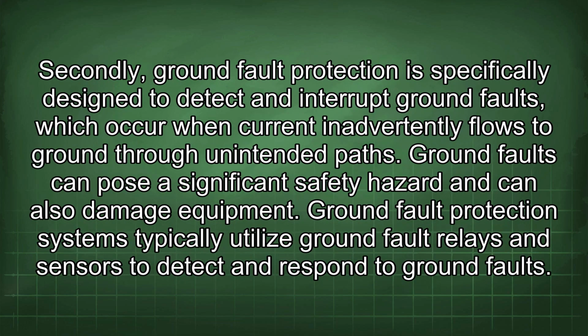Secondly, ground fault protection is specifically designed to detect and interrupt ground faults, which occur when current inadvertently flows to ground through unintended paths. Ground faults can pose a significant safety hazard and can also damage equipment. Ground fault protection systems typically utilize ground fault relays and sensors to detect and respond to ground faults.